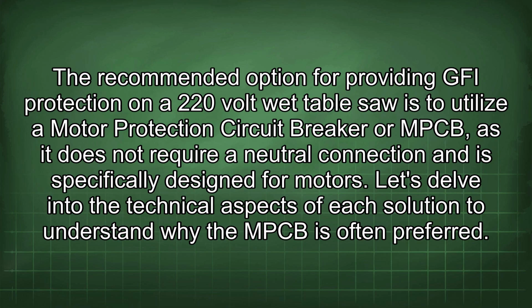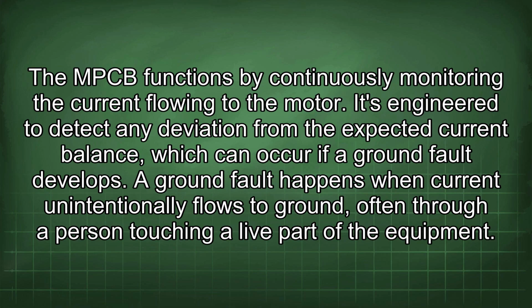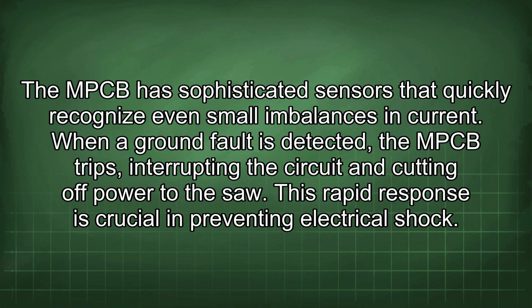Let's delve into the technical aspects of each solution to understand why the MPCB is often preferred. The MPCB functions by continuously monitoring the current flowing to the motor. It's engineered to detect any deviation from the expected current balance, which can occur if a ground fault develops. A ground fault happens when current unintentionally flows to ground, often through a person touching a live part of the equipment. The MPCB has sophisticated sensors that quickly recognize even small imbalances in current. When a ground fault is detected, the MPCB trips, interrupting the circuit and cutting off power to the saw. This rapid response is crucial in preventing electrical shock.